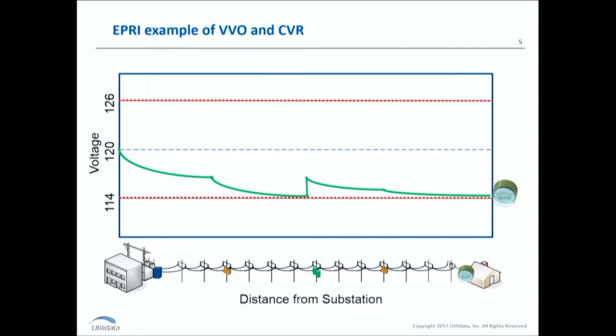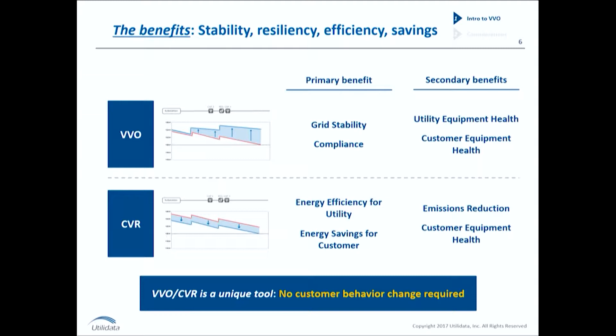So why do we do it? Often it gets reduced to VVO being for energy efficiency, but there's actually a wide range of benefits that come with this lowering and flattening. First and foremost is grid stability—keeping the lights on, preventing equipment failure, and letting customer devices operate most effectively, which means operating at a consistent, and where possible low, voltage within bounds.